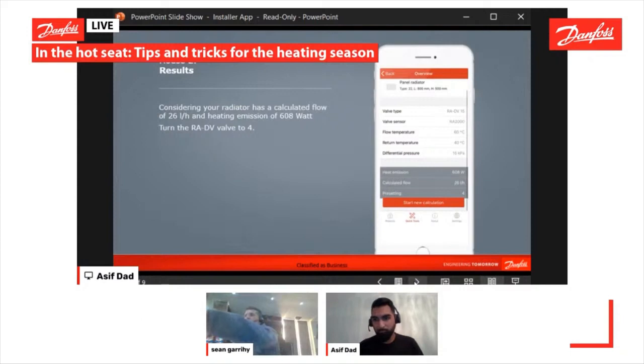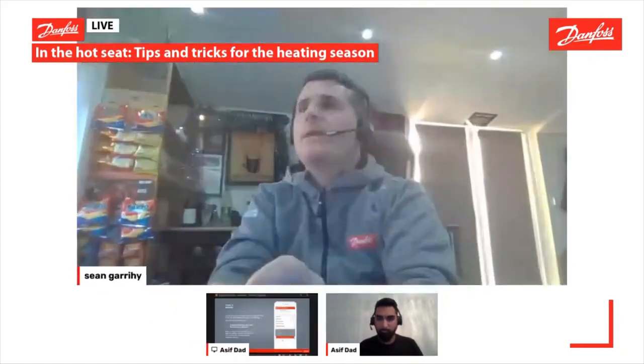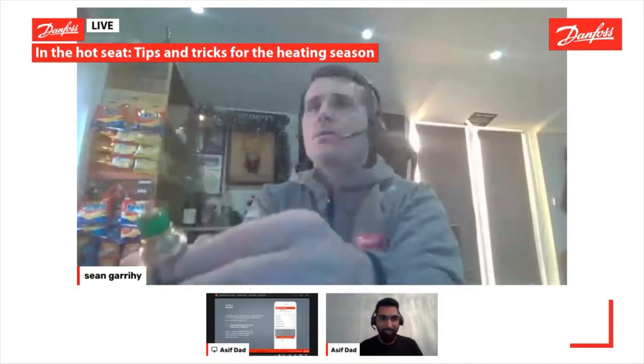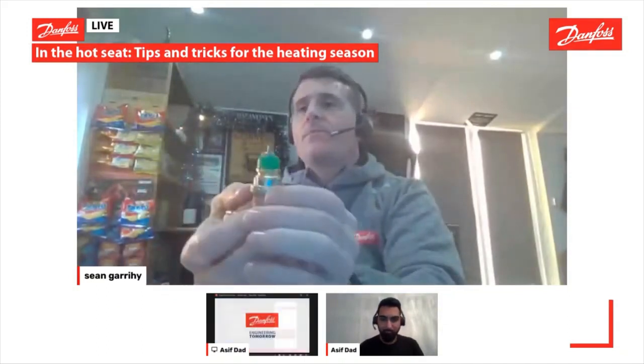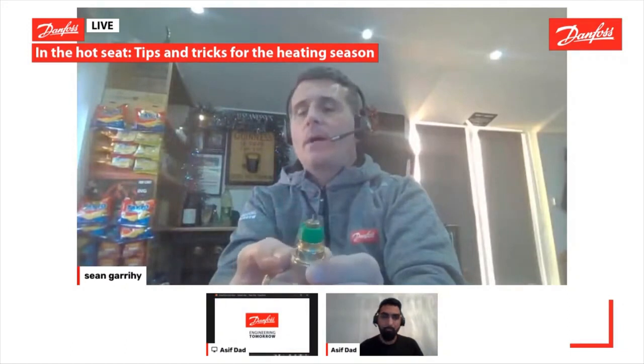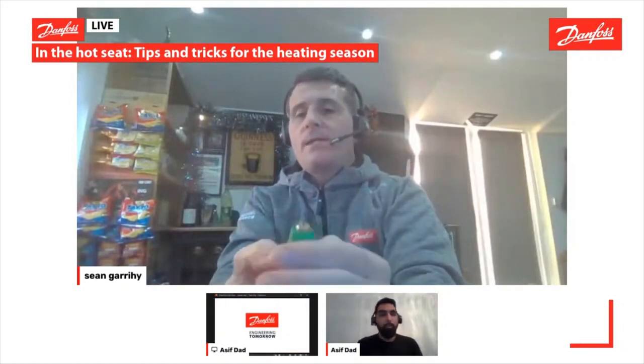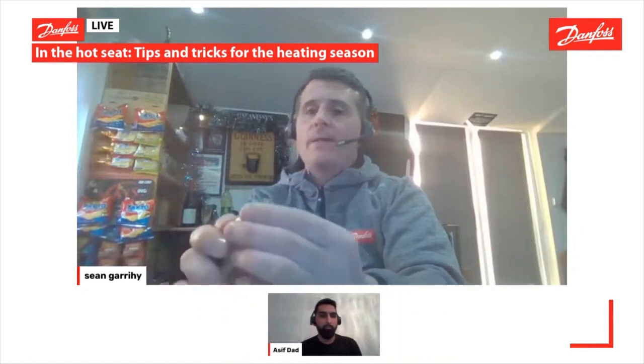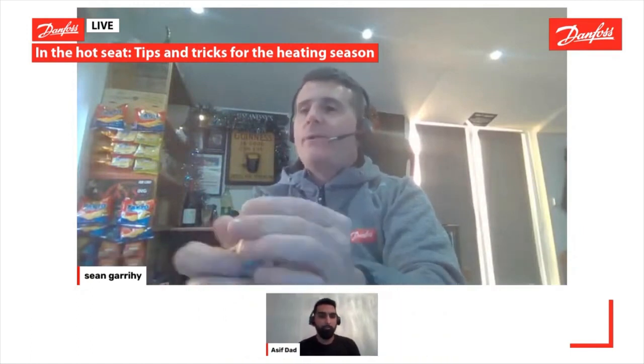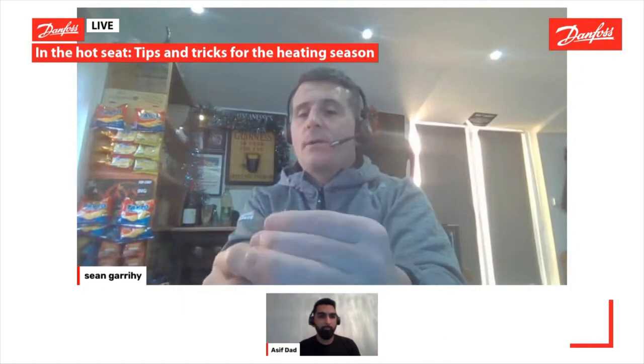If you look at the bottom, it's a presetting 4. So I don't know if you can see here. It's probably the easiest. I don't know if we've got another slide that can show. We don't. So okay, I will try and show you. There's a little arrow here. It's probably quite difficult to see on my camera, but in live it's so easy to see. And at the top there's a green collar, and it says N27. So basically all you do is turn the little collar to 4 above the arrow. You can't see that unfortunately, but that is basically your radiator preset.